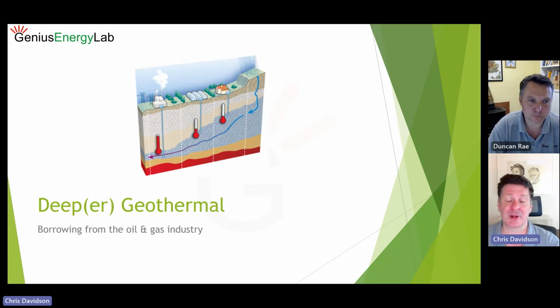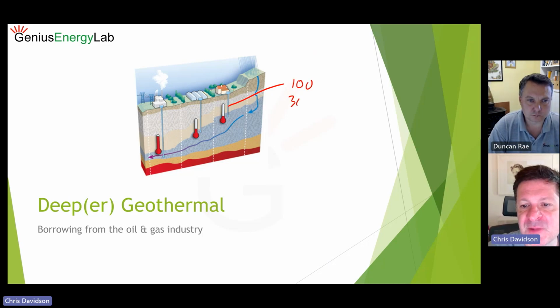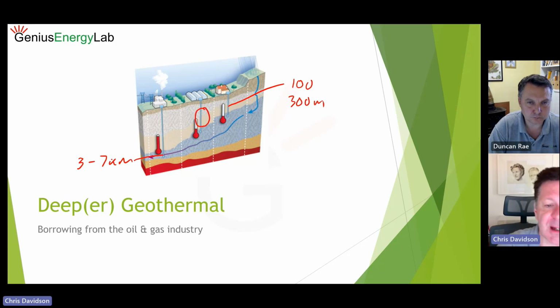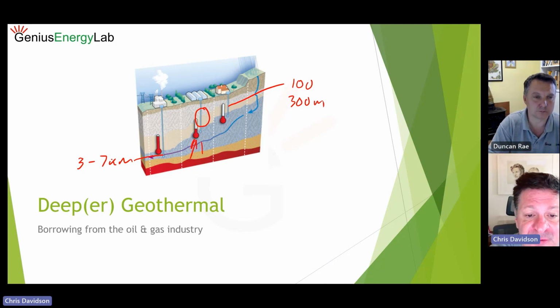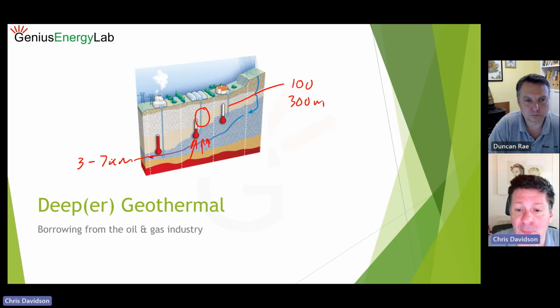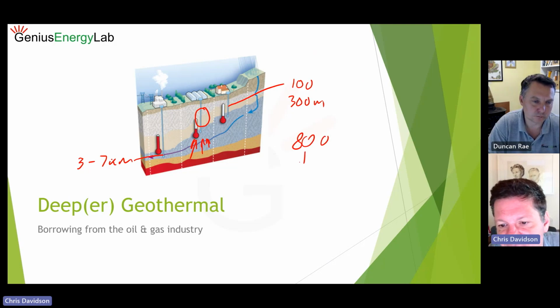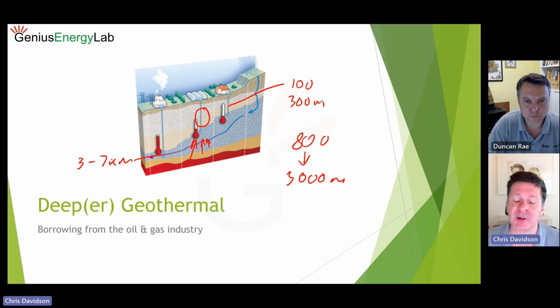Deeper geothermal is one of the big buzzes at the moment in the industry. As I mentioned earlier on, we are normally drilling between 100 and 300 meters down for our normal systems. To get to electrical generation in the UK, you're talking 3 to 7 kilometers. So what we're now interested in is this middle ground here, where we're getting higher temperatures than at those shallower depths. So we're getting more of a geothermal gradient, and we're also getting more per borehole. The depths I'm talking about here, 800 meters to 3 kilometers, are where we're getting significant increases in temperature. These systems are starting to be installed now, and it's a very interesting development in the marketplace.